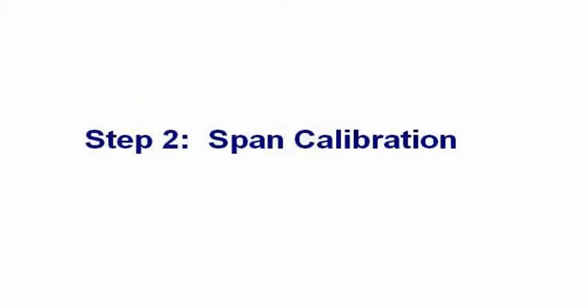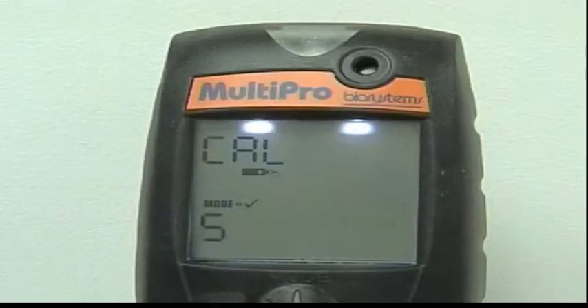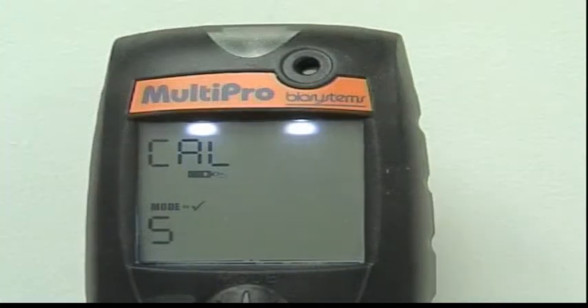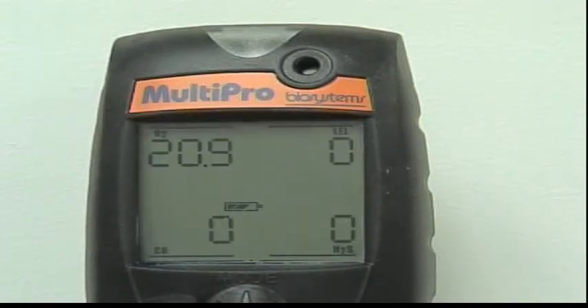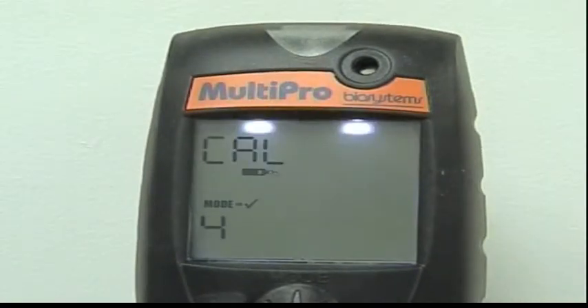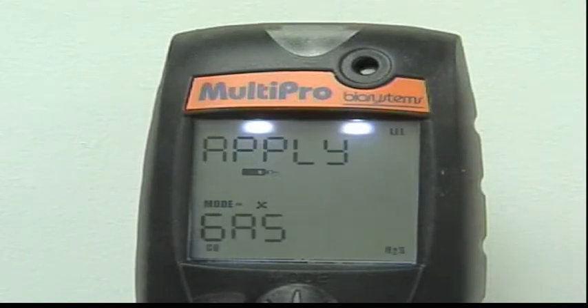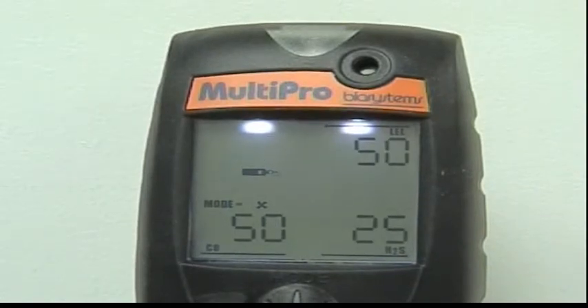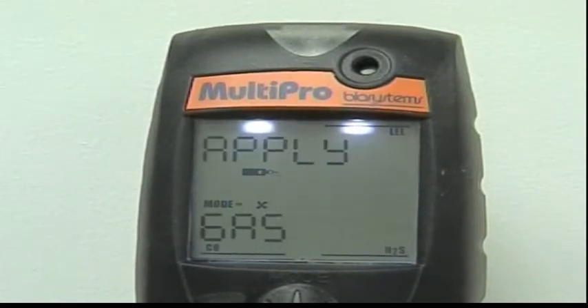Once the fresh air calibration has been successfully completed, the instrument will proceed to the automatic span calibration sequence. The instrument will display the word CAL along with a calibration gas bottle icon, and another 5-second countdown will begin. If the mode button is not pressed within 5 seconds, the instrument will return to normal operation. Press the mode button before the end of the 5-second countdown to initiate the span calibration adjustment. Apply gas will then be shown alternately with the expected concentrations of calibration gas for each sensor.